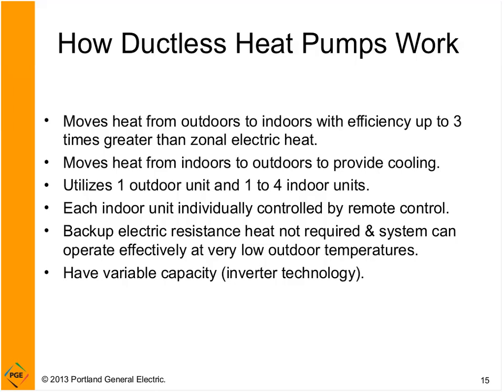And for ductless heat pumps, one feature that you're looking for, and most of the product that's available out there today has this, is variable capacity or inverter technology. You might think of your air conditioner, or if you have a standard heat pump in your home, the units cycle on and off. And that's not the most efficient way to operate a compressor. The most efficient operation is to vary the capacity for the heating and cooling demand, and that's what variable capacity does. So it may be a time of moderate outdoor temperature in the heating season, and it's only operating at partial capacity. It's just slowed down, so it really reacts quickly to the heating and cooling needs in the apartment or wherever it's installed.